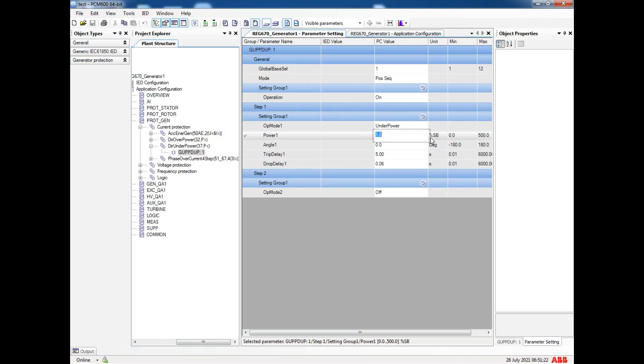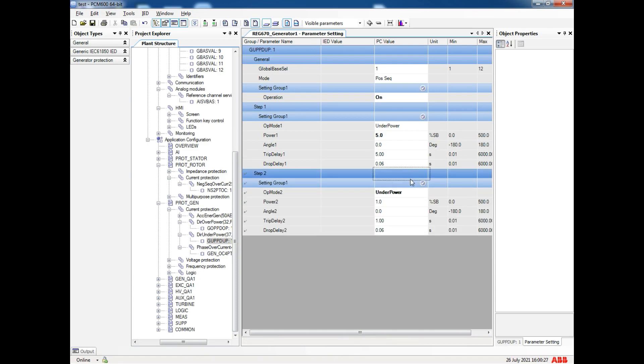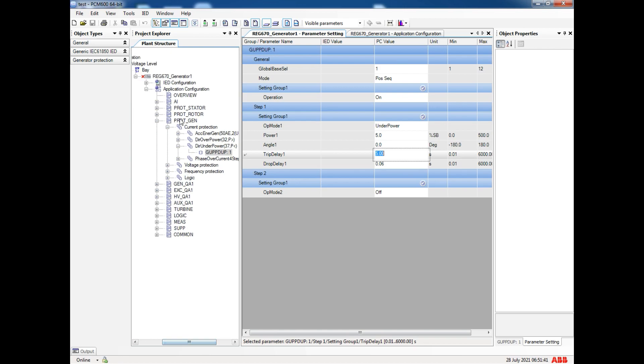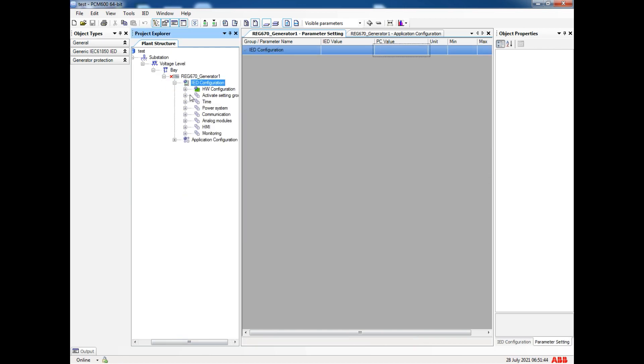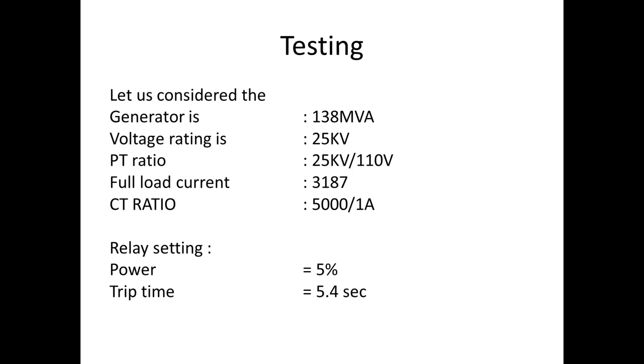In relay settings we have to note two things. One is power — it is in percentage, which is 5 percentage. Second one is trip time, which is 5.4 seconds. Here we can also use two stages if we need. One is power in MVA — we have to set this as our generator power in relay settings, from there it will take 5 percentage as per our settings.